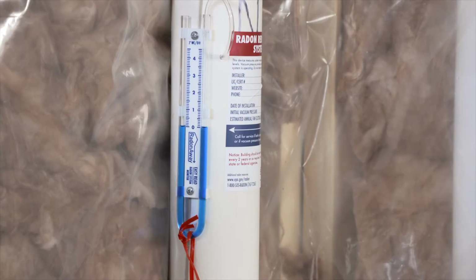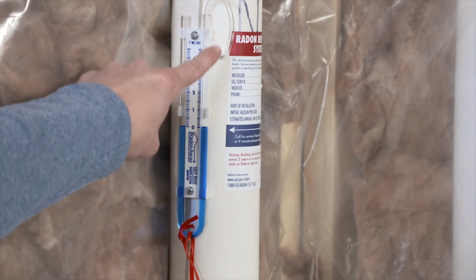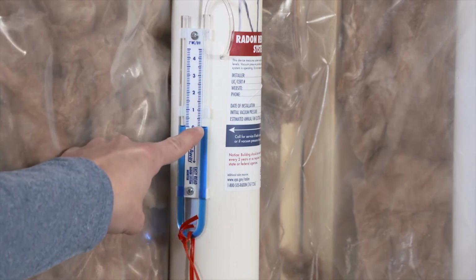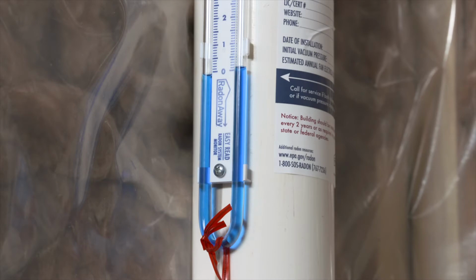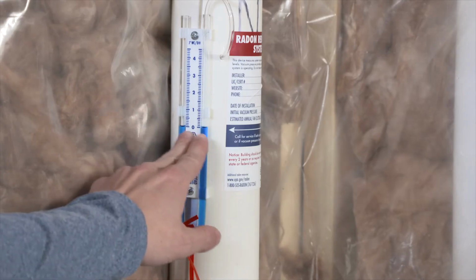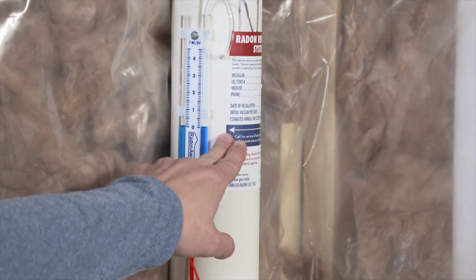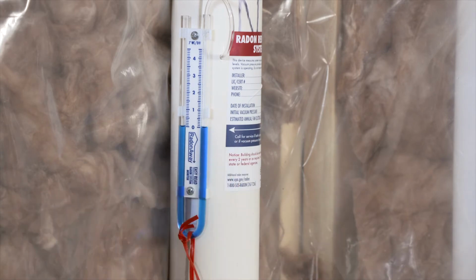Right now both levels are at 0 because you don't have the fan system operating. That's correct. As soon as the fan starts running, this tube will pull the blue liquid up and you'll see it's functioning, which is an indication the system's working as it should. If it ever does go to zeros, you've got blue lines on the side telling you to call a certified mitigator to have it serviced.